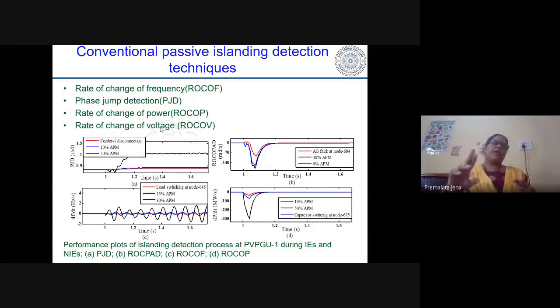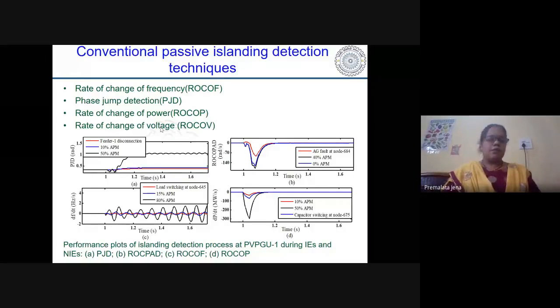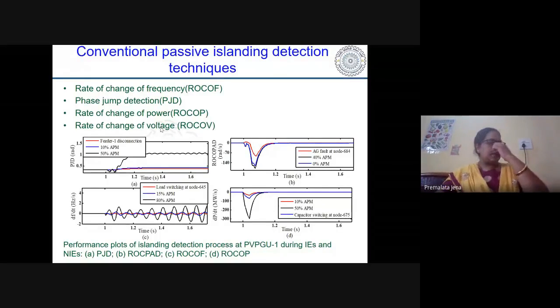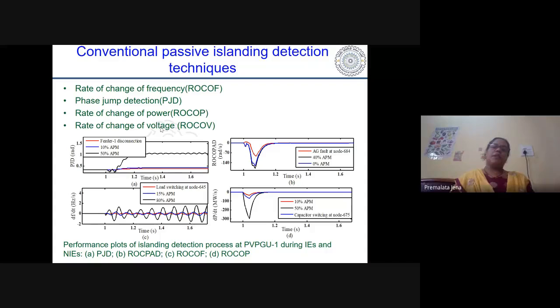That change - you take it, and you take the rate of change of that voltage and frequency, and when it crosses a certain threshold range, it will detect the islanding situation. So the major drawback of this conventional passive islanding detection technique: first, if the power imbalance or mismatch is less than 10%, these techniques fail.